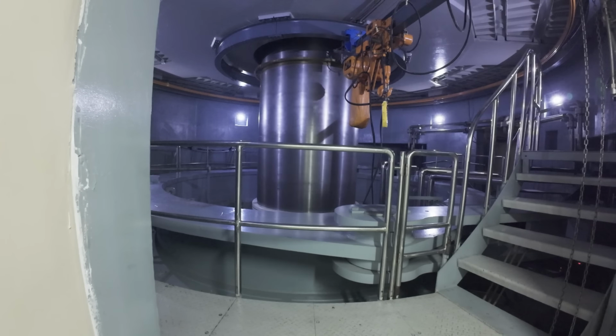Step 9. Initially, the thrust bearing still depends on the high pressure oil lifting system, but as rotation speed increases, something important begins happening naturally. Hydrodynamic lubrication develops. Think of this as the moment the machine stops walking and starts surfing on a wave of oil. The rotating shaft drags oil into the wedge-shaped film beneath the bearing surface. That oil film becomes strong enough for the rotor to effectively float without direct metal contact.